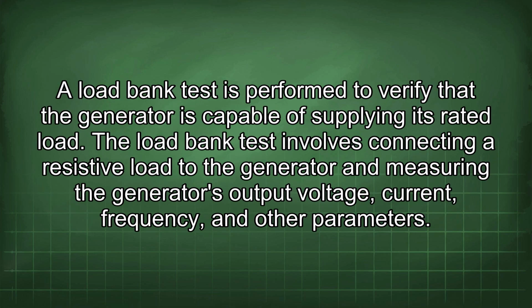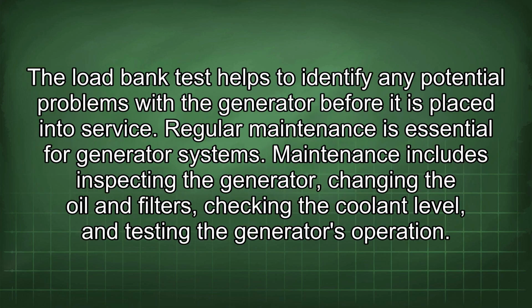A load bank test is performed to verify that the generator is capable of supplying its rated load. The load bank test involves connecting a resistive load to the generator and measuring the generator's output voltage, current, frequency, and other parameters. The load bank test helps to identify any potential problems with the generator before it is placed into service.